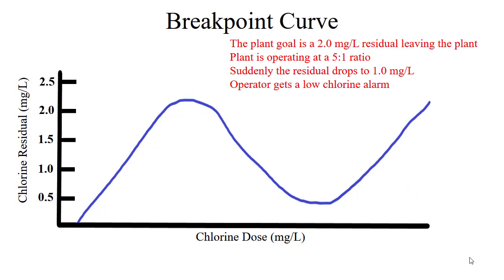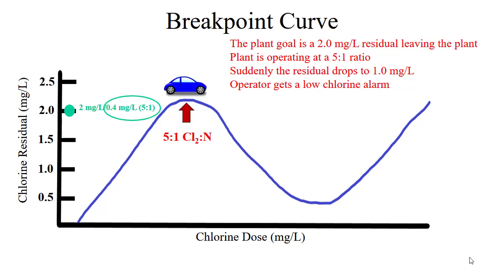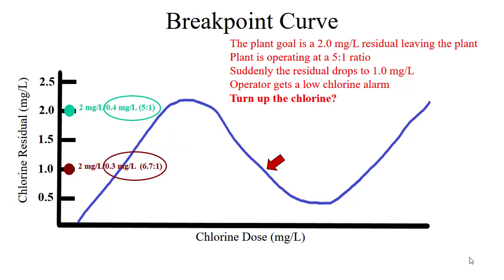You are an operator alone on shift at 2 o'clock in the morning — because problems always occur in the middle of the night or late on a Friday afternoon — and you get a low chlorine alarm. The plant effluent water has a total chlorine residual of 2 mg/L with an ammonia dose of 0.4 at a 5-to-1 ratio, and suddenly the plant effluent total chlorine residual drops to 1 mg/L. Should the operator immediately turn up the chlorine feed rate? The answer is no. The first thing to do is investigate the chlorine and ammonia feed rates to ensure both are correct before making any major adjustments. In this scenario, there was a leak on the ammonia feed pump, and the ammonia feed rate decreased from 0.4 to 0.3 mg/L. This change moved the plant from a 5-to-1 ratio to a 6.7-to-1 ratio. If the operator had immediately turned up the chlorine without checking both feed pumps, the plant could have moved to breakpoint, putting it out of compliance and causing a water quality problem.